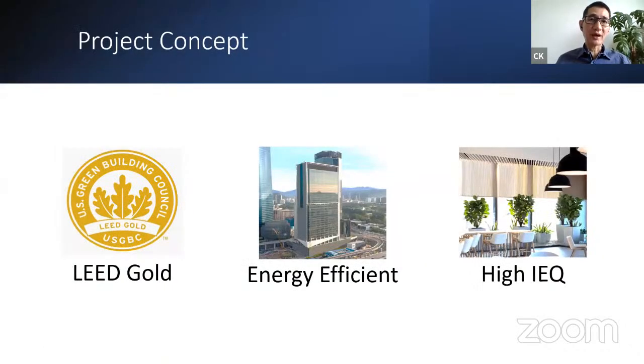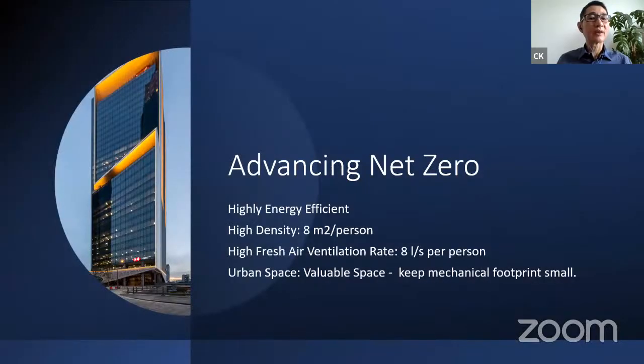The project concept is to get a LEED Gold version 4, and it's highly energy efficient and also has very high indoor environment quality. I will talk more about that as we go on. In terms of advancing net zero, like I said, it's highly energy efficient. This building is also very high density for Malaysia. It's designed for 8 meters squared per person, and it has a very high fresh air ventilation rate of 8 liters per second per person, more of a European fresh air rate than the ASHRAE fresh air rate, which is much lower.